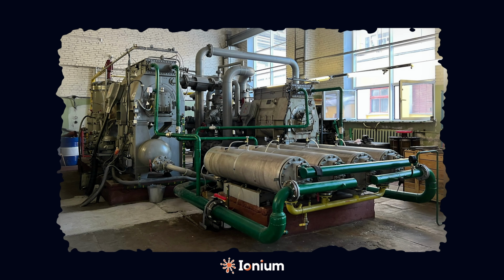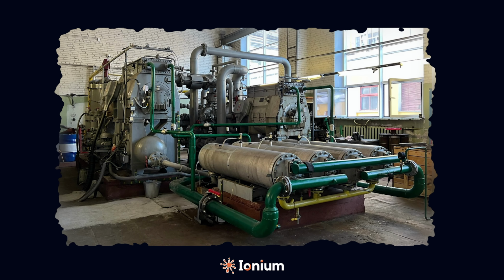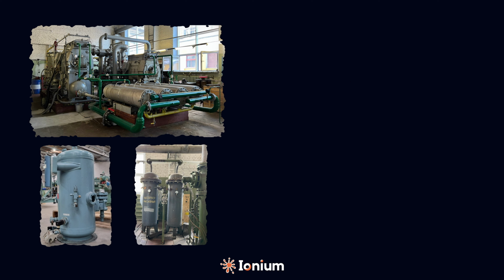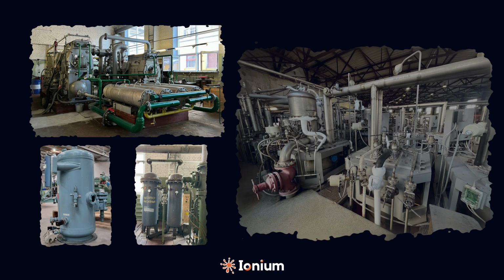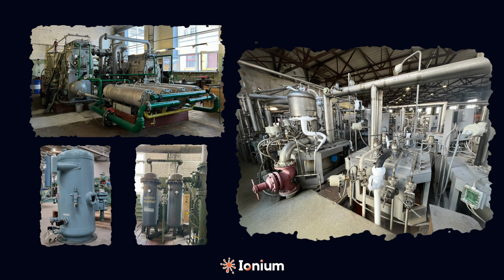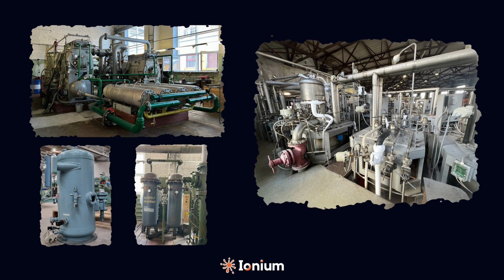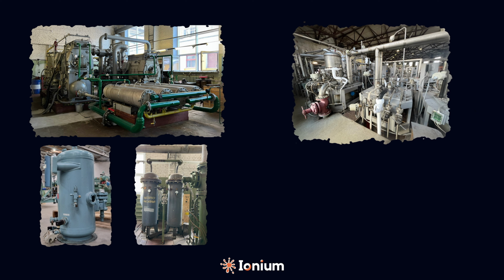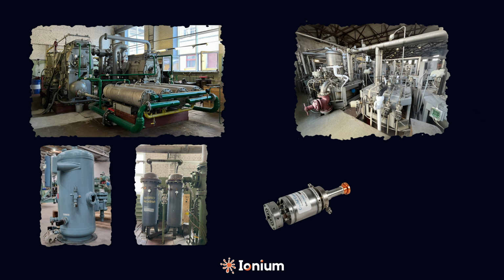Compressed helium, produced using screw oil-filled compressors, oil separators and adsorption purification devices, is used across various industries. Their primary use is in generating compressed helium, which is then used as a working fluid in variously designed cryogenic systems, ranging from those using traditional cycles with pre-cooling and expanders, to others designed as cryogenic machines, operating based on the reverse Stirling or Gifford-McMahon cycles.